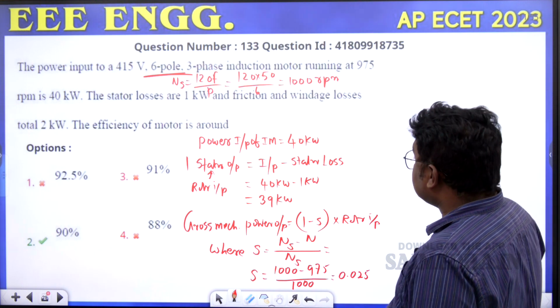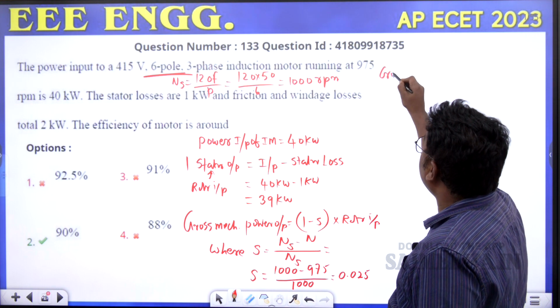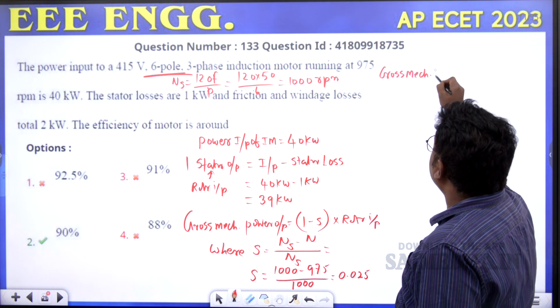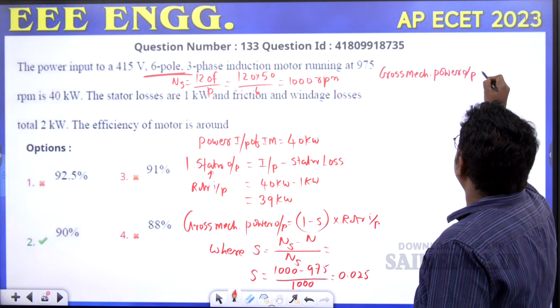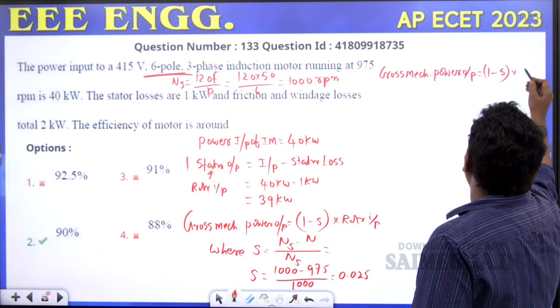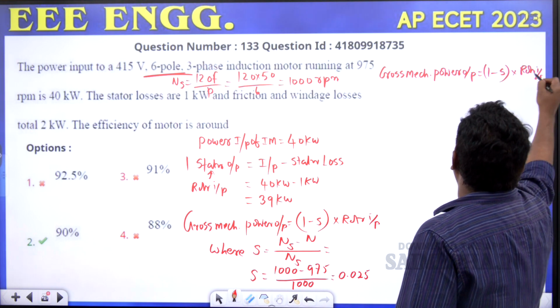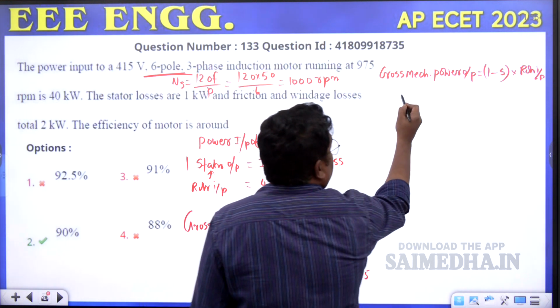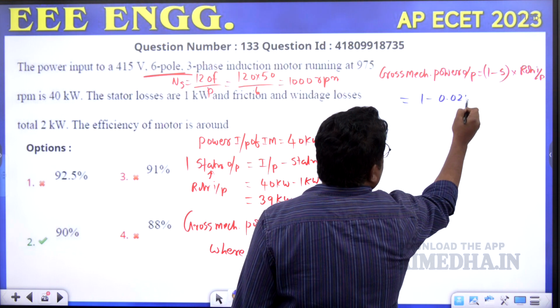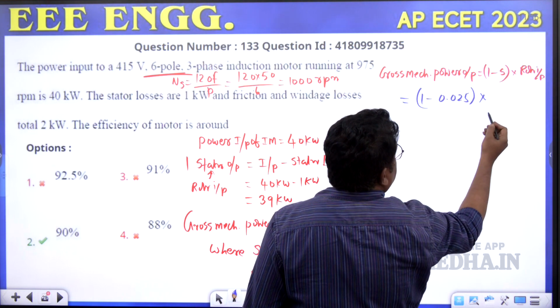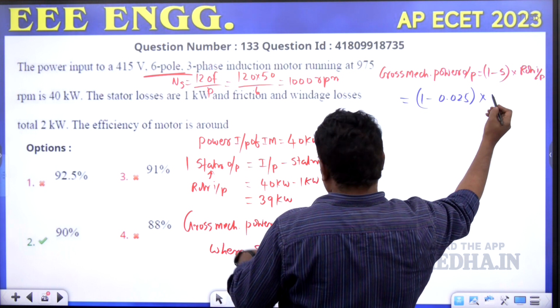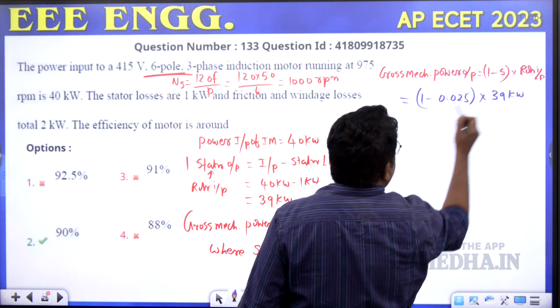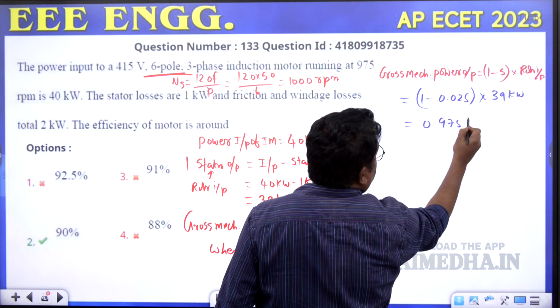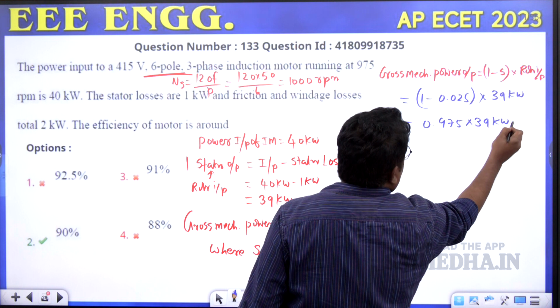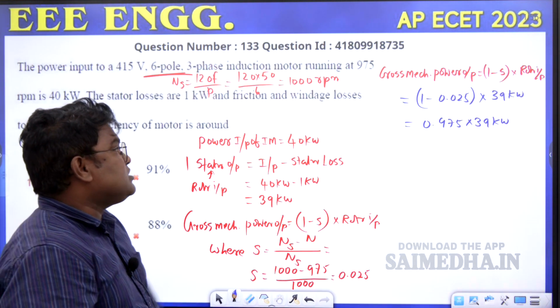Now after getting S, we can find the gross mechanical power output of the motor. It is equal to 1 minus S into the rotor input power. So it is equal to 1 minus 0.025 multiplied by the rotor input of 39 kilowatts. Now this is equal to 0.975 into 39 kilowatts. Got it? So this is the gross mechanical power.